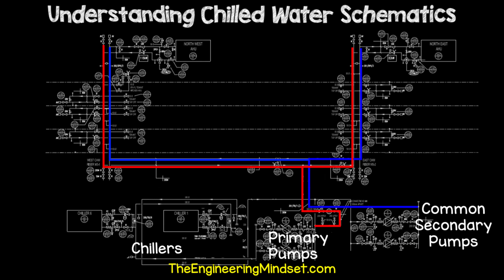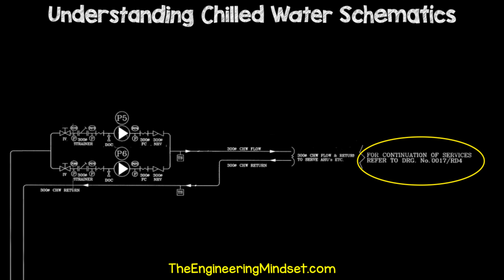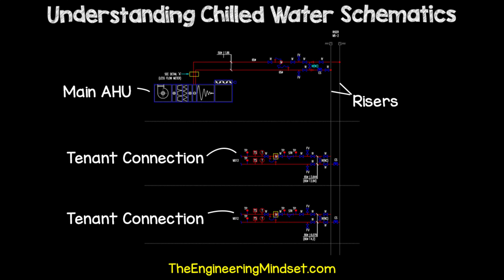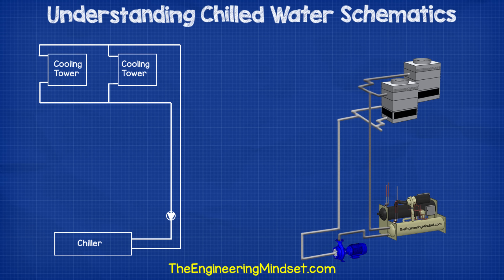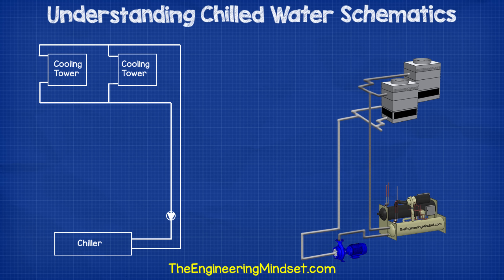Usually they will not display every air handling unit and fan coil unit that's connected to the system. Sometimes they will show the connection to the main AHUs, and other times they will refer you to a separate drawing if you want to see this detail. If the building rents floors out to tenants and the tenants have full control over the fit-out of that area, then the drawing will just show the connection from the main risers over to the tenant's space, and anything after that is up to the tenant's fit-out contractors, who should provide the landlord with a copy of their own drawings. Additionally, you should remember that these drawings do not show every bend or the exact route through the building — they are simply a flat 2D representation of the system.